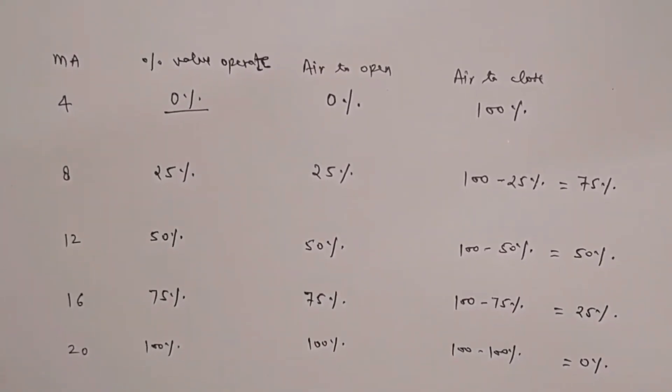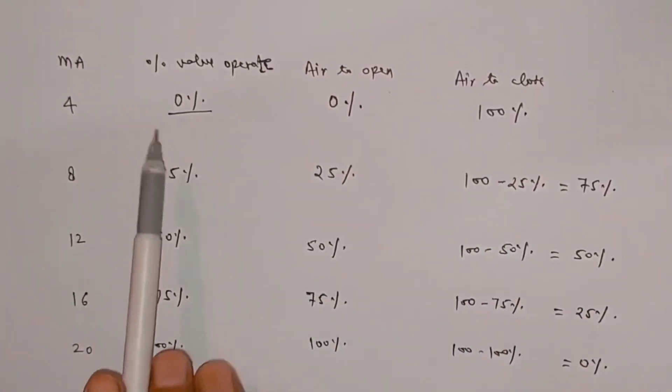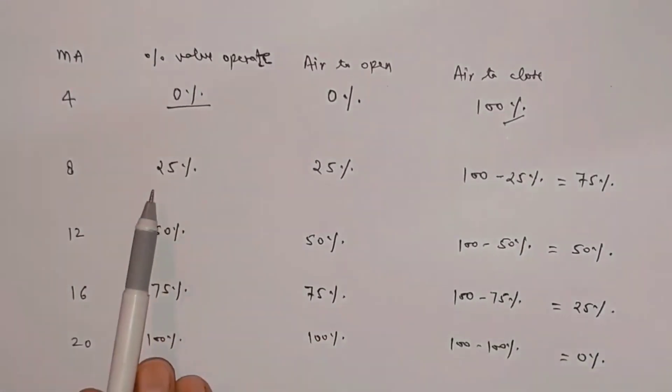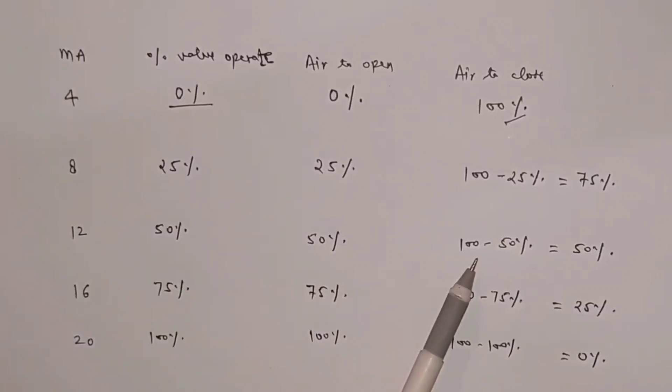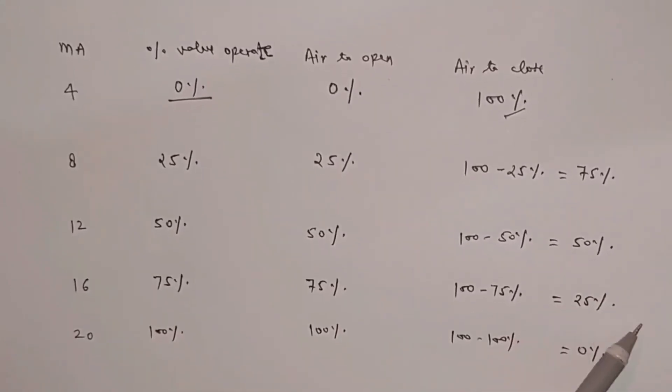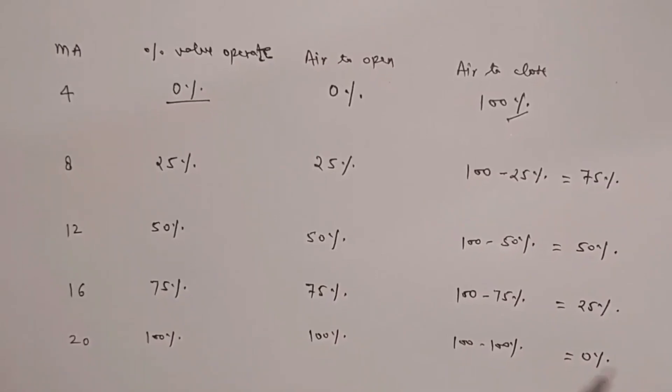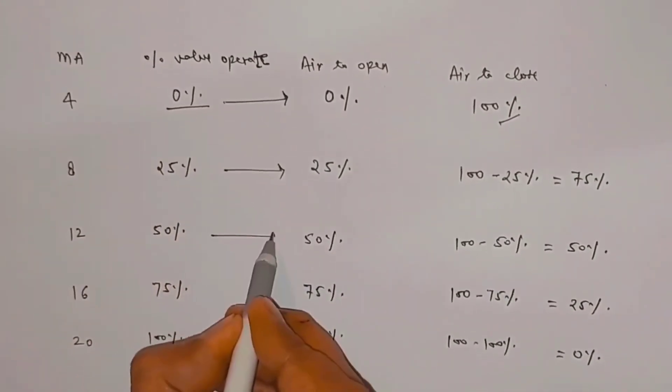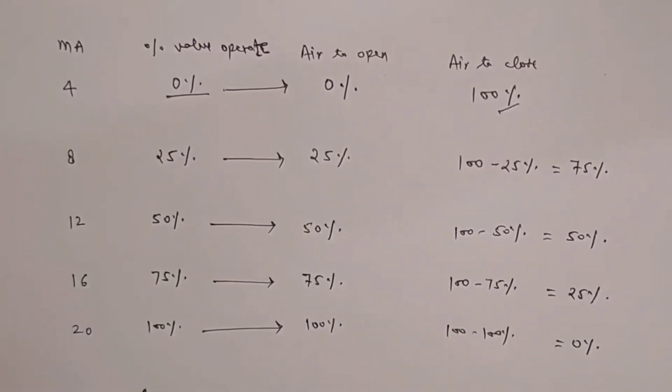Friends, here you need to keep in mind that when we see the opening of air to close control valve, we will subtract it from 100. Like at 0% it was 100 minus 0, means 100%. At 25%, it will be 100 minus 25, means 75%. At 50%, 100 minus 50, means 50%. At 75%, 100 minus 75, means 25%. And at 100%, 100 minus 100, means 0%. And air to open control valve will operate exactly like this: 0% at 0, 50 at 50, 75 at 75, and 100% at 100.